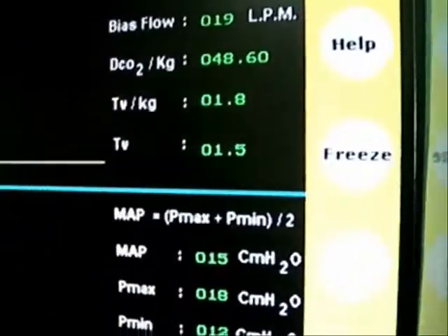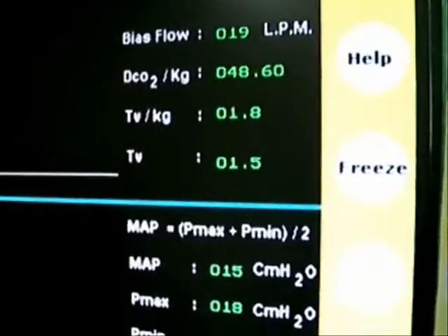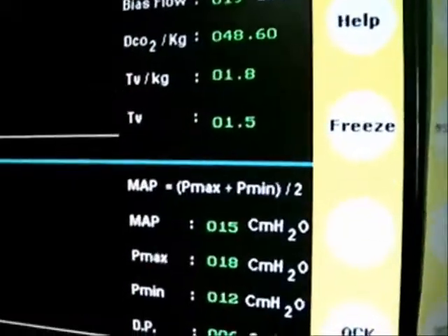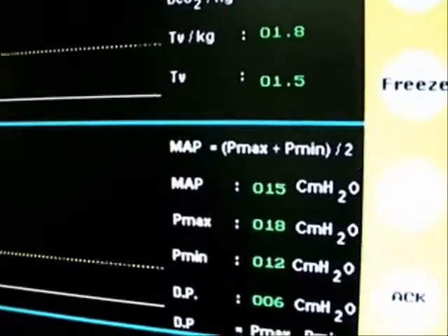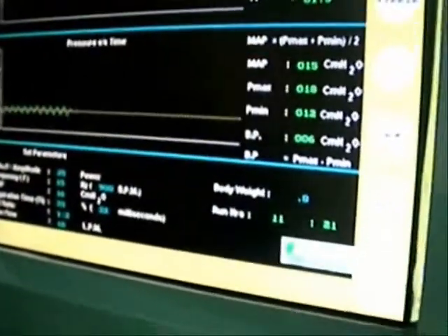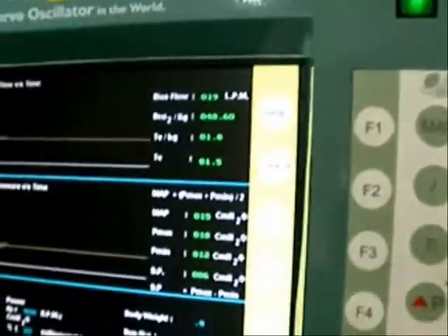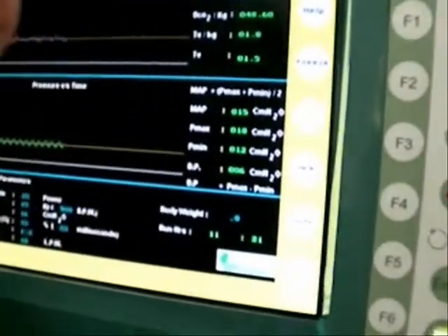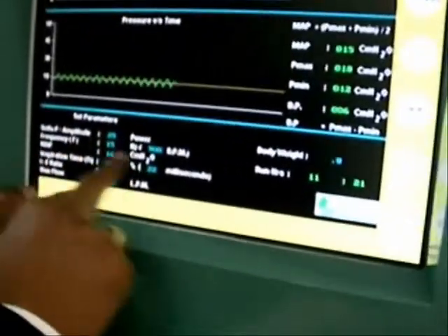So if you want to achieve a MAP of 15, I'll open my orifice in such a way that your MAP is maintained, and simultaneously the bias flow is sufficient, and vice versa also. So that's the beauty. The clinician doesn't need to adjust the bias flow. All he needs to do is to set the amplitude, the frequency, the MAP, and the inspiration time. The rest is done automatically.